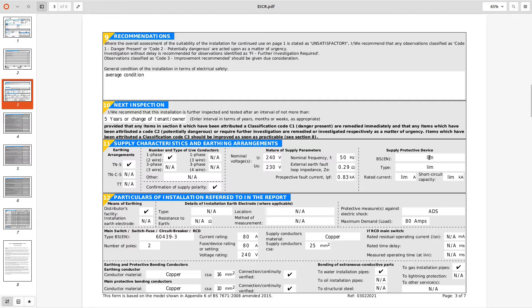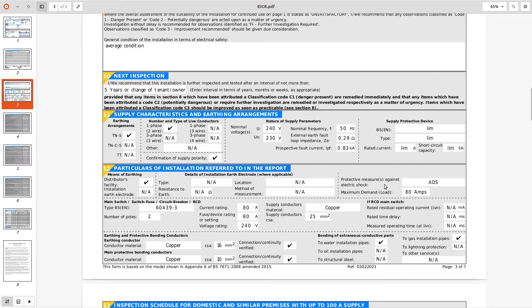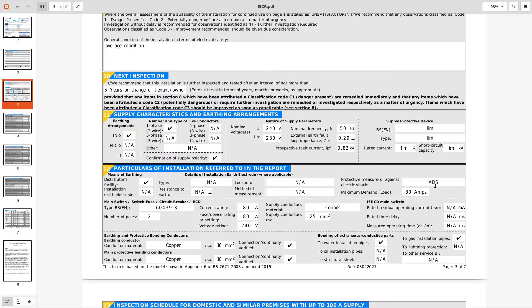Limitations applied for these protective devices that's the suppliers cut out there may have not have been any writing on the fuse which is sometimes the case on older properties. Distributors facility that looks good. Method of electric shock against electric shock sorry is ADS automatic disconnection of the supply.